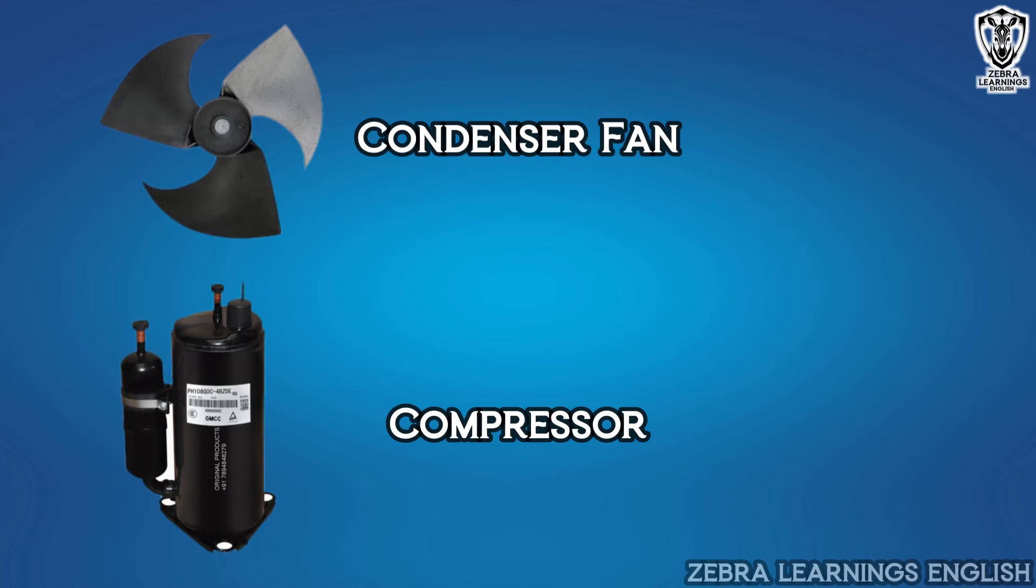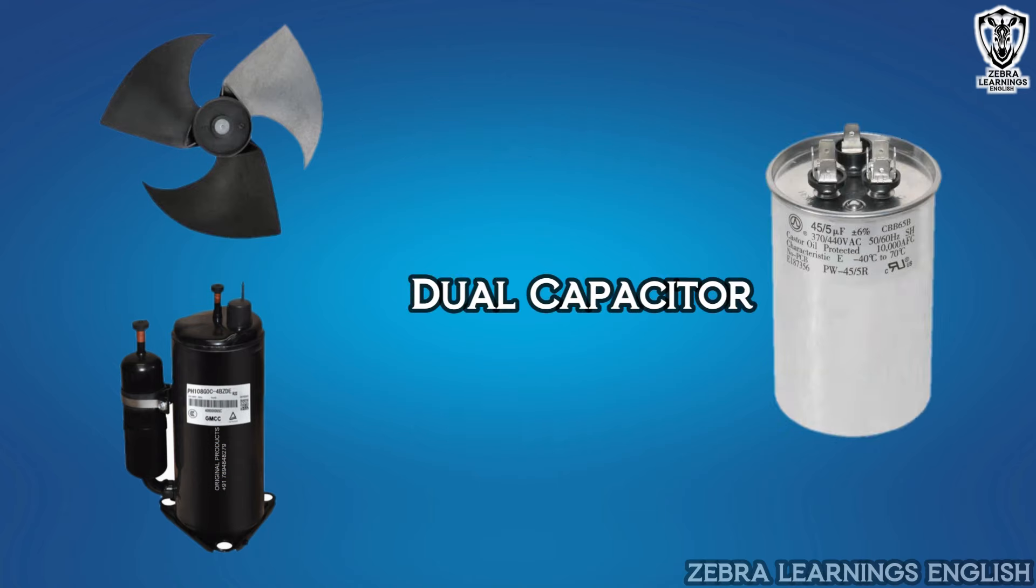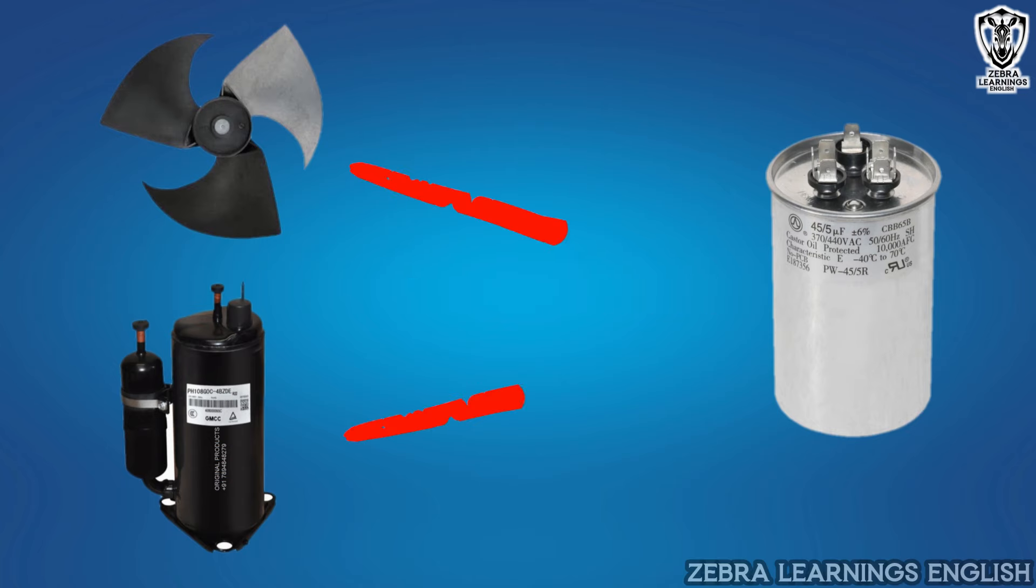Dual capacitors are used in most recent AC units. A dual capacitor means that the same capacitor is used for both components. Dual capacitor has three terminals: common terminal, fan terminal, and herm terminal.